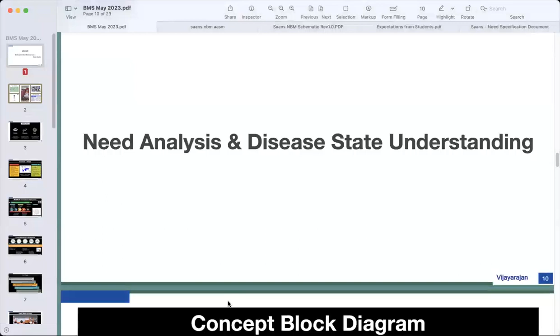Now, I told you what exactly the problem is. So how do we try to solve the problem? Let me see whether I can make this slightly bigger. The compressed oxygen comes here. Air comes here. It gets mixed in this manifold unit. We have a flow sensor and an oxygen sensor. Then we also take the pressure from the, because another thing is, see, this is our device. And after that, we have a lot of tubes going all the way to the patient, the baby. That also introduces additional resistance to the air going in.